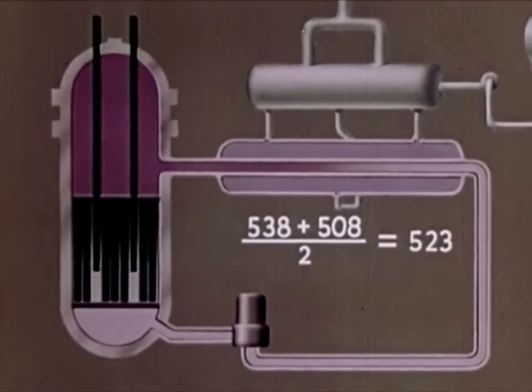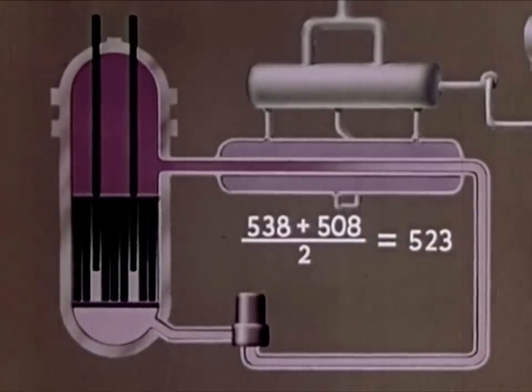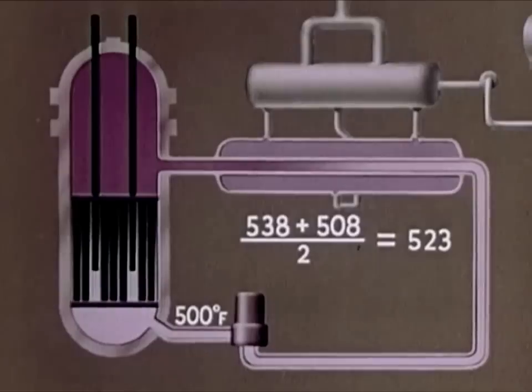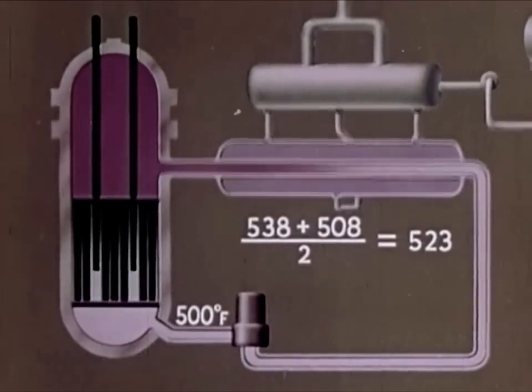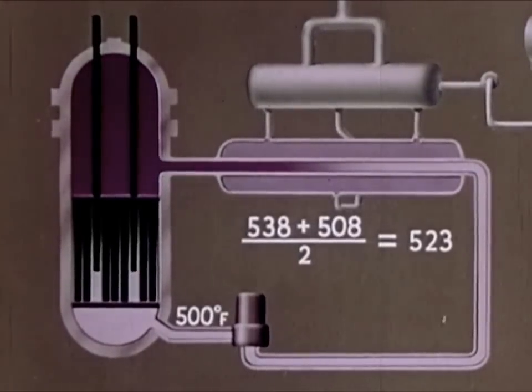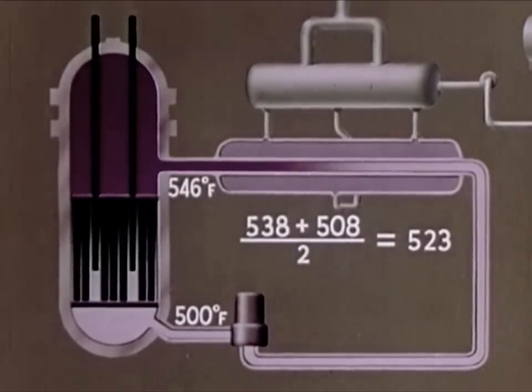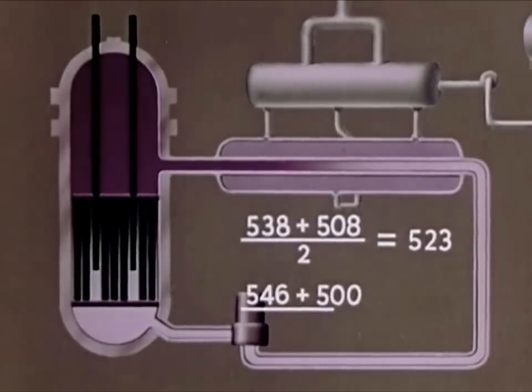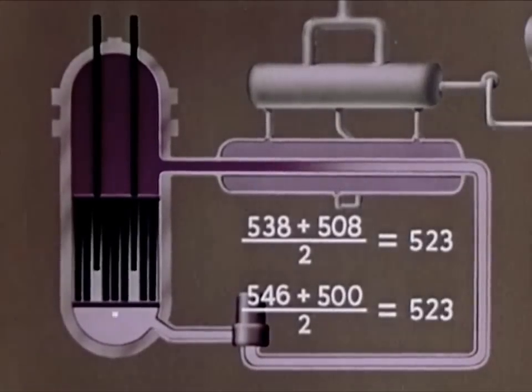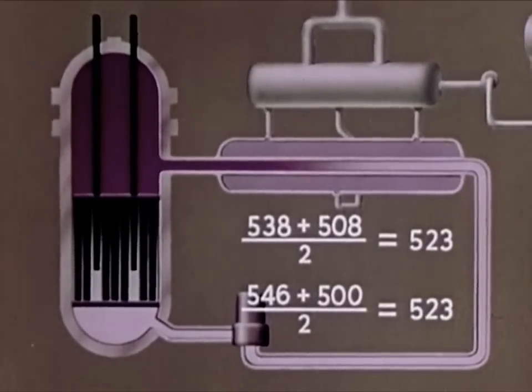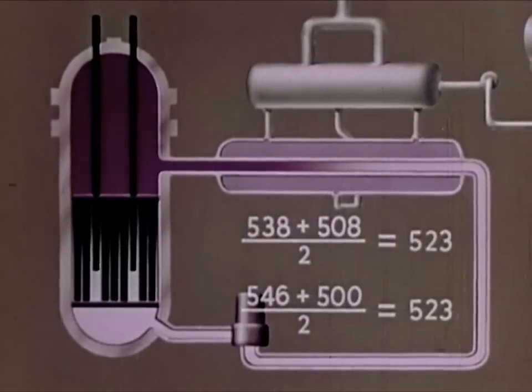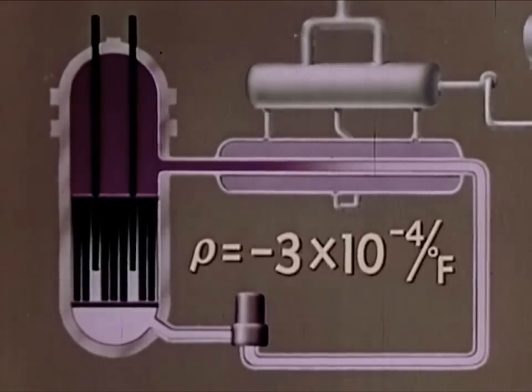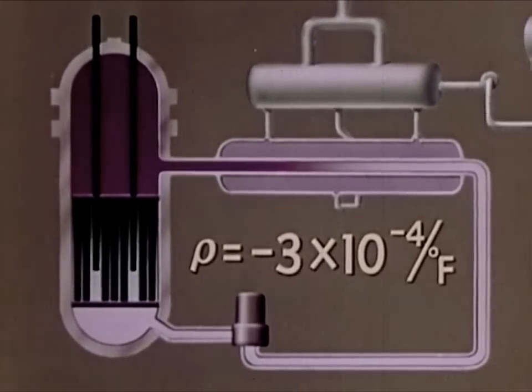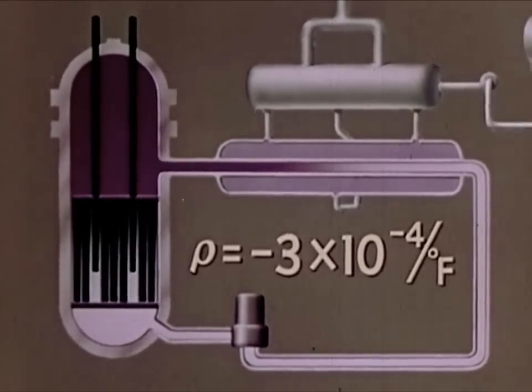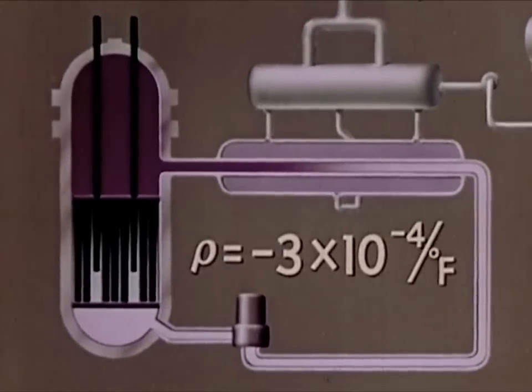With increased steam demand caused by an increase in electrical output, the inlet water temperature may drop to 500 degrees. The reactor automatically increases power output, and the outlet temperature automatically increases to 546 degrees. Note that the average temperature remained constant, making the reactor plant virtually self-regulating. The value of this temperature coefficient was found to be minus 3 times 10 to the minus 4 per Fahrenheit degree at operating temperature, a value which agrees well with the calculations of this quantity.